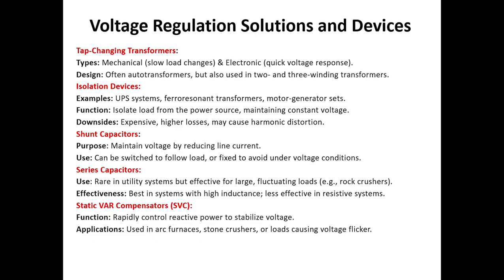Then we think about the isolation devices, such as UPS systems, ferroresonant transformers, and motor generator sets. These devices can also be used for voltage regulation or for the improvement of voltage regulation, and they are expensive. The UPS is an uninterruptible power supply. Ferroresonant transformers are transformers we can use to isolate the devices. A motor generator set is also used as an isolation device for voltage regulation purposes. All these devices are more expensive.